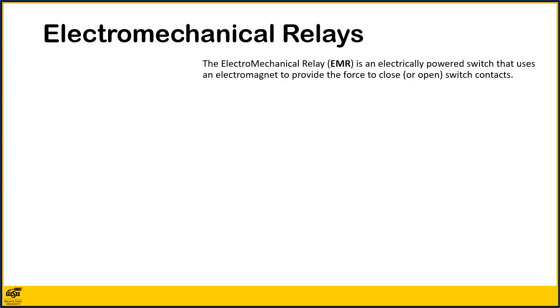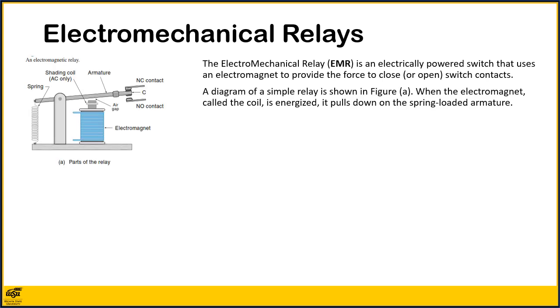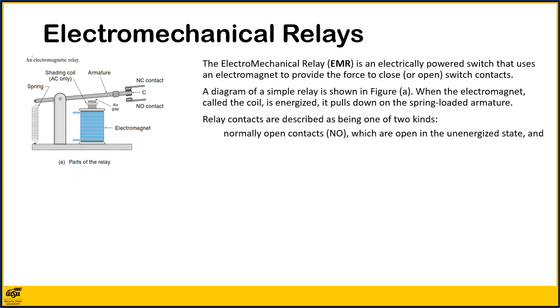The electromechanical relay, or EMR, is an electrically powered switch that uses an electromagnet to provide the force to close or open switch contacts. A diagram of a simple relay is shown in Figure A. When the electromagnet, called the coil, is energized, it pulls down on the spring-loaded armature. Relay contacts are described as being one of two kinds: normally open contacts, NO, which are open in the unenergized state, and normally closed contacts, NC, which are closed in the unenergized state.